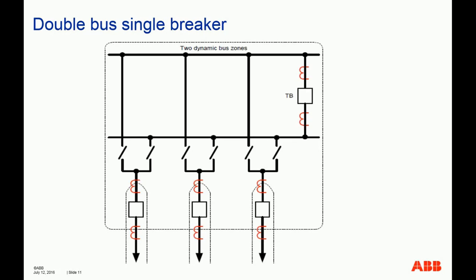Double bus single breaker, of course, is very common nowadays. Typically we see a lot of this in modern GIS switchgear. It is flexible. You can freely balance the load and transfer the load between the two buses, the first bus on top and the second bus at the bottom. Because of the two disconnects here, you can connect the feeders freely to each of the buses, following a certain operating procedure, of course.